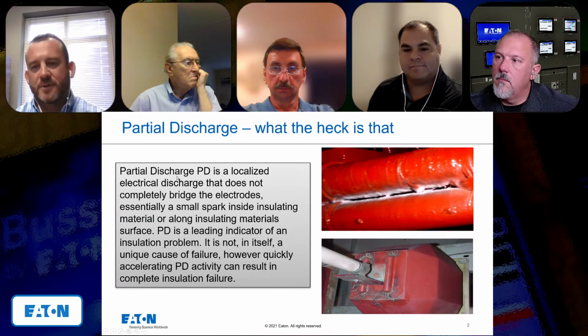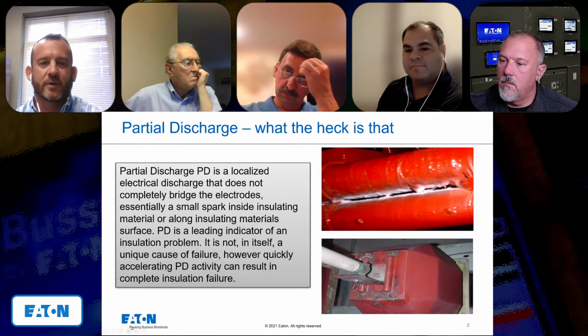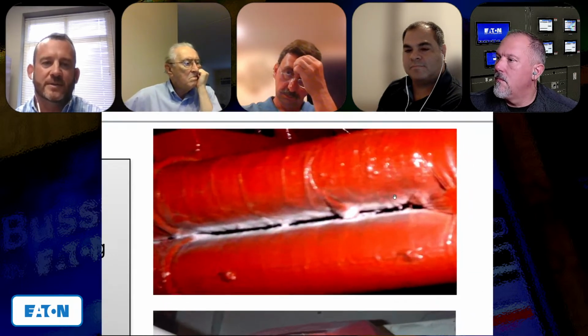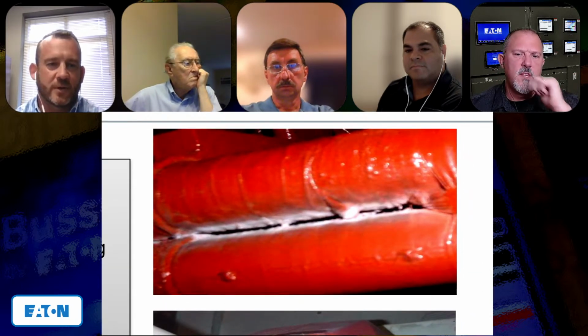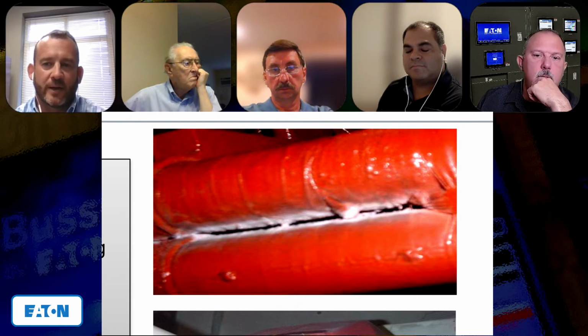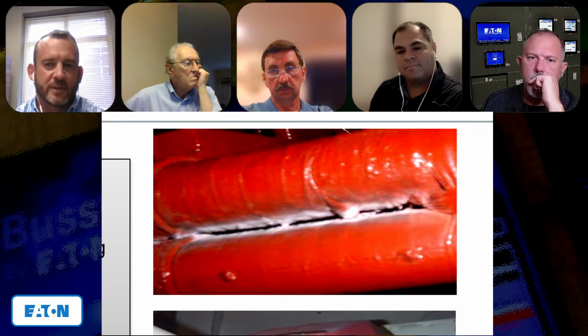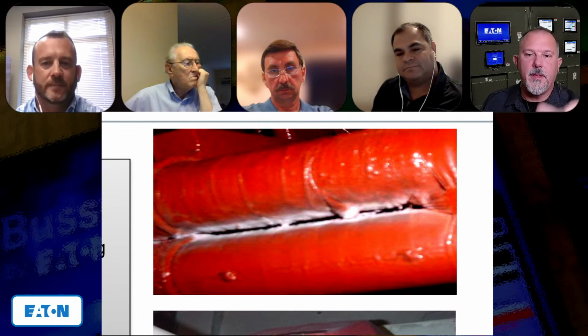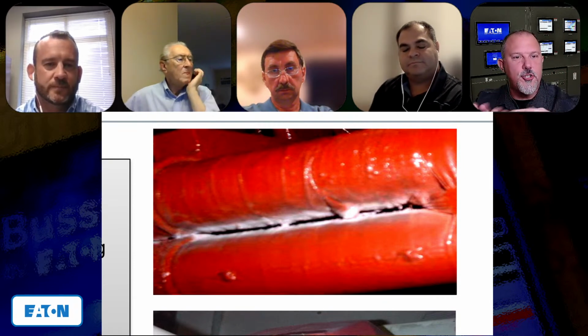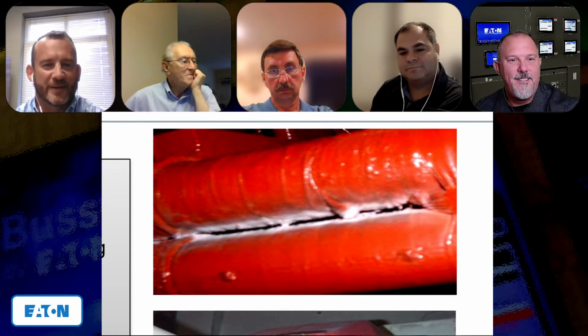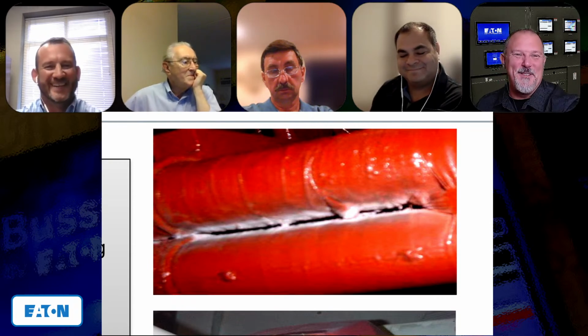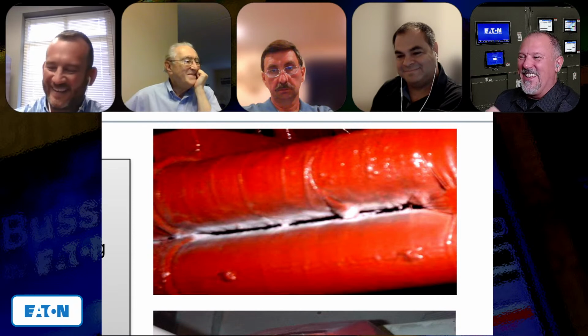The top picture shows a bit more of a breakdown - that's due to corona, and you'll see this a lot more commonly in electrical switchgear that has moisture in it. That's the insulation breaking down, creating that white powder in between the phases. Oh, I thought maybe that was powdered sugar we put on there. No, that's a perfect insulator. I like it.